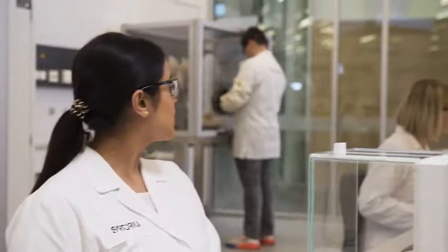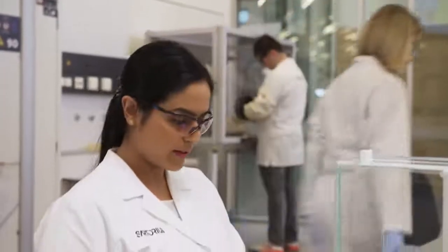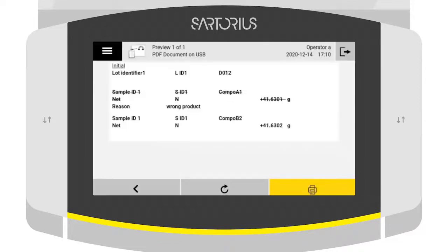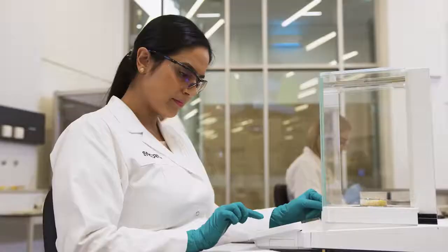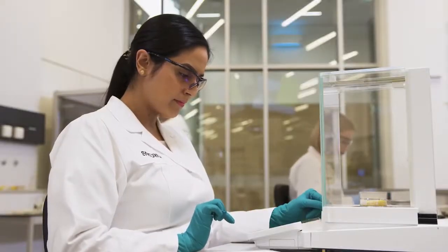All results with the relevant metadata are automatically recorded by the Cubis II balance according to ALCOA principles. Before the report is generated, you can review it and, if necessary, mark any incorrect weights together with a comment. The user can then sign the report with his or her electronic signature.